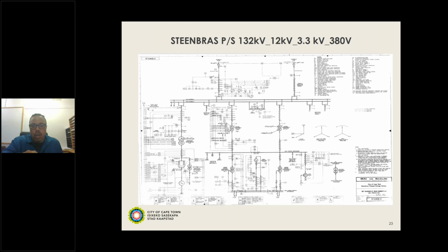In the middle of the drawing we have our two station transformers, stepping 132 down to 3.3 kV, and towards the bottom our 3.3 kV bus, which is where all the local supply gets run from. On the far right of that bus, at the bottom, we have what we refer to as our pony motor, which runs from the 3.3 kV supply. You may be able to see the variable resistance on it - we have what we call a liquid starter on the pony motor, which varies the resistance to match what the pony motor needs to do.